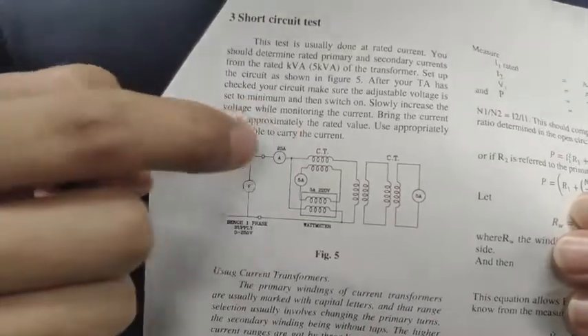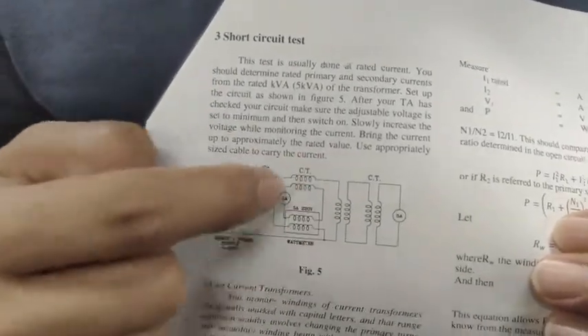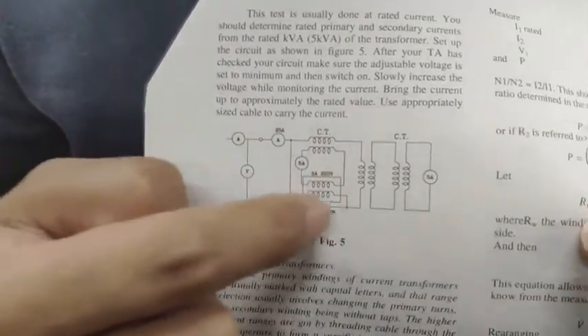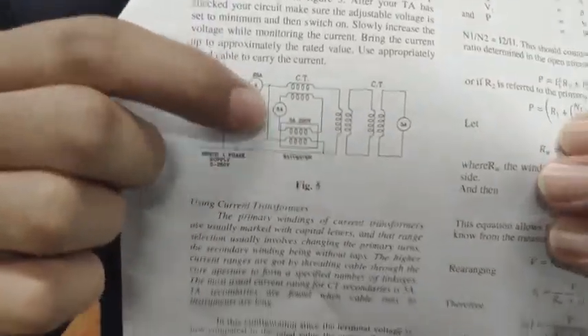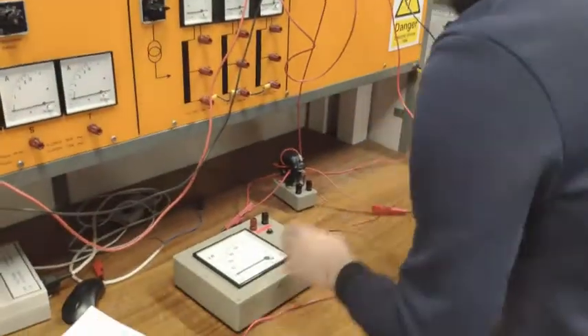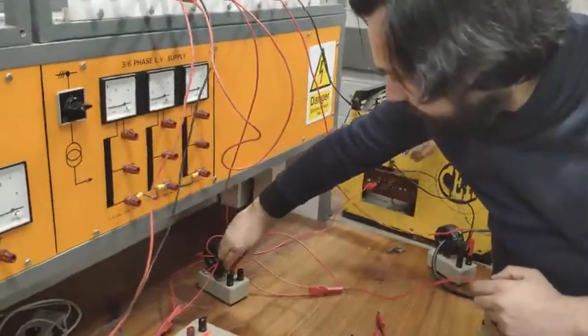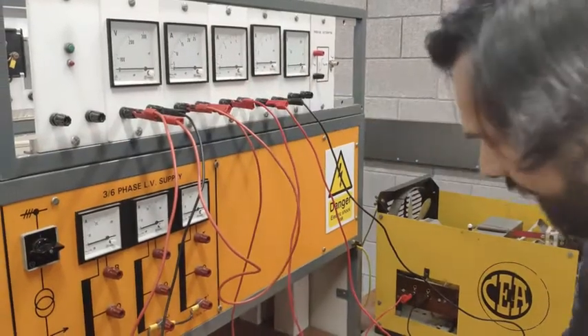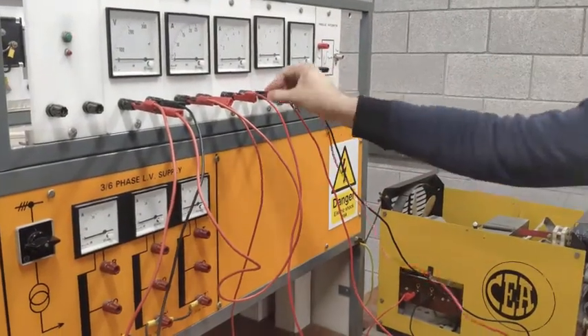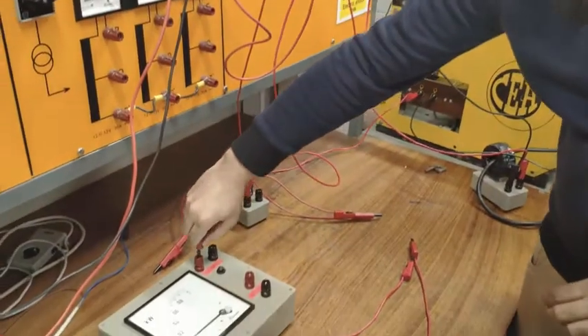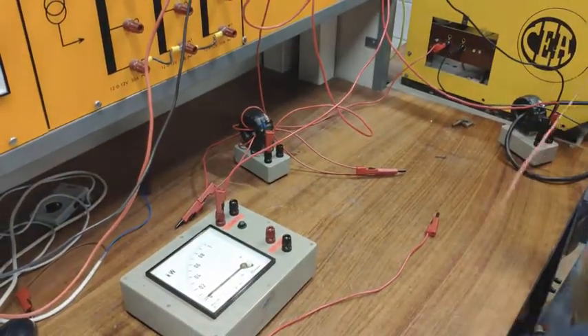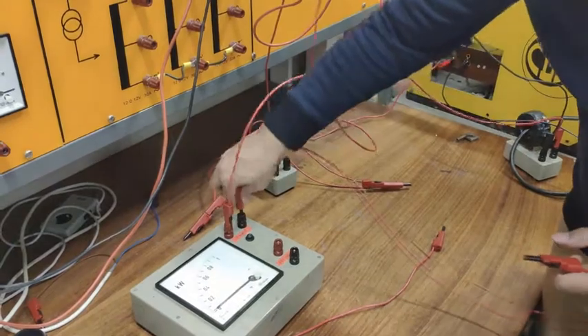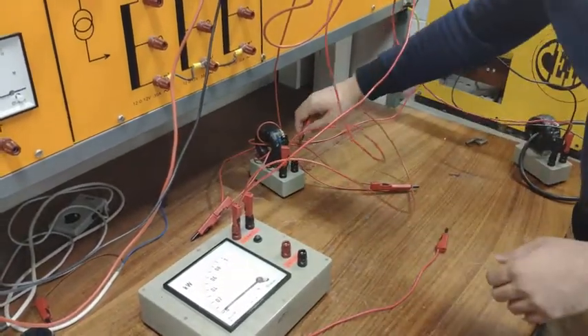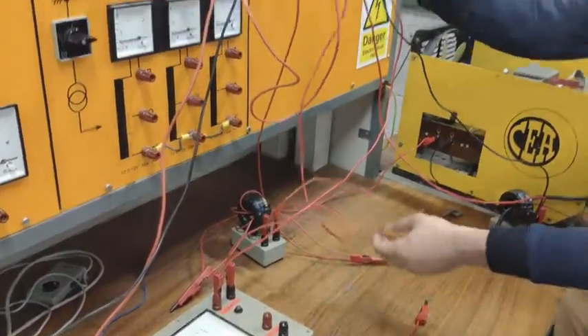You go inside the CT, you connect the winding to the CT. Now for the secondary winding, you have to make a loop through 2 ammeters. One is of the wattmeter and the other one is a 5 ammeter. So if you come out of here, you go to the 5 ammeter, and when you come back, you go into the ammeter of the wattmeter, and then you connect it back to the CT. So this completes the loop.